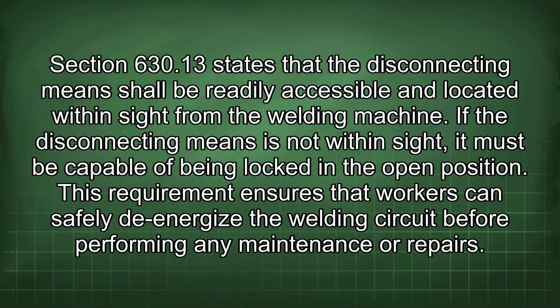Section 630.13 states that the disconnecting means shall be readily accessible and located within sight from the welding machine. If the disconnecting means is not within sight, it must be capable of being locked in the open position. This requirement ensures that workers can safely de-energize the welding circuit before performing any maintenance or repairs.